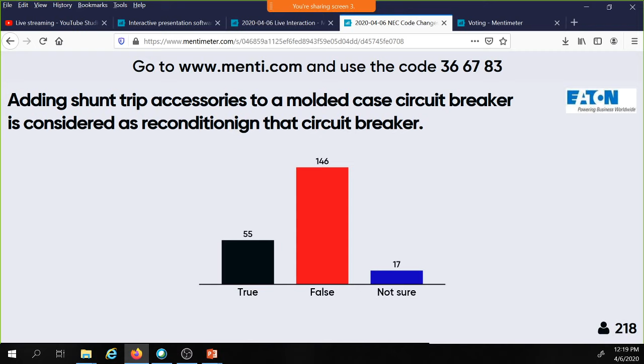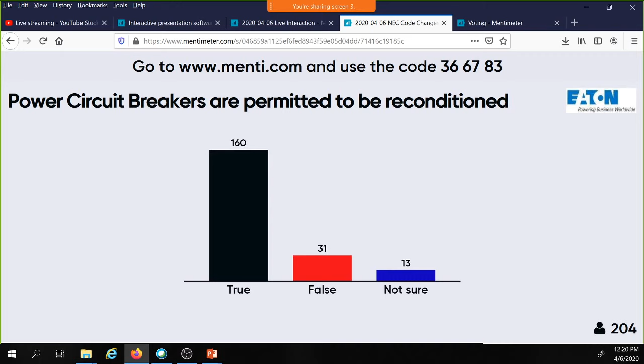Power circuit breakers are permitted to be reconditioned. 160 said true, 31 said false, 13 not sure - that is a true statement. Power circuit breakers are permitted, and we do that as an industry a lot. We recondition circuit breakers, motors, and a lot of different pieces of equipment. The National Electrical Code made some changes, which we're going to go through, to help you understand what can and cannot be reconditioned, and more importantly, when the activity you're doing on a piece of equipment falls into the definition of reconditioning.